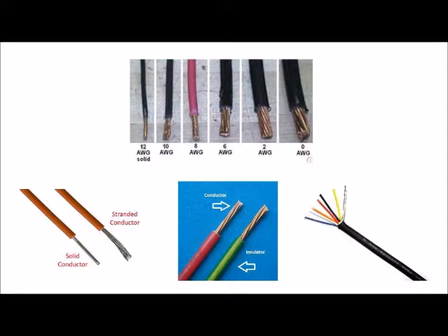They come in a variety of diameters, called gauges, that vary depending on the power required and the distance to the load. The smaller the gauge number, the larger the diameter. Most access control conductors are in the 18 to 24 gauge range. Conductors can generate heat, so it's important in system design to account for the wire gauge.